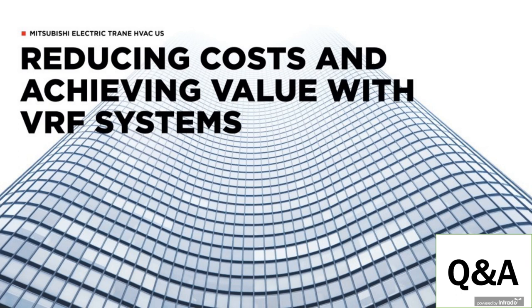Thanks, Kevin. Yeah, the retrofit and new construction mix is pretty even in my area. We get into both, and VRF offers a great solution because it's modular and scalable in either application. But in retrofit in particular, we have a 2-pipe heat recovery system, which minimizes your space requirements for running all the pipe work and ducting associated, right? You can do ductless systems in spaces that normally don't have high floor-to-ceiling space. And so it becomes a very lucrative way to redesign some of these and update some of these older buildings.